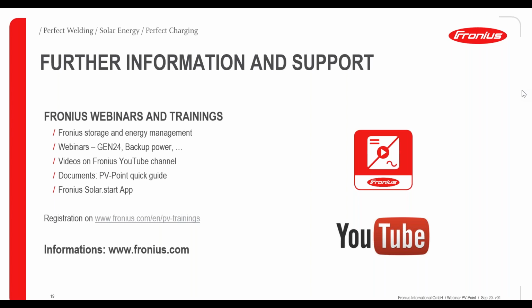So first question is about the automatic switchover of the PV point. So what is the status of the PV point when the grid is available? First of all, when the grid is available, so when there is no grid blackout, the PV point is deactivated. So the PV point gets activated as soon as the grid fails. So when there is a grid blackout, then the PV point will be activated by the inverter. As soon as the grid comes back, then the PV point is deactivated again, and waits for its next activation when there is a grid blackout again. So under normal circumstances, the PV point is not available.